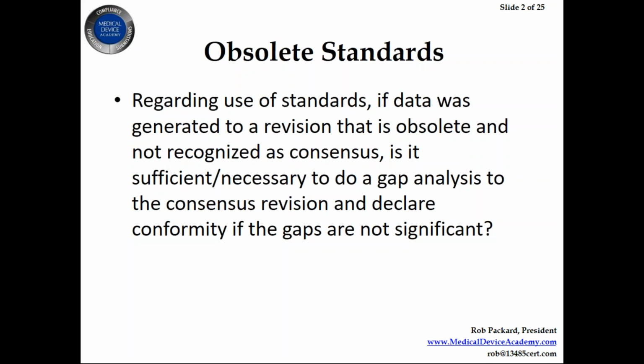So we had to redo all our testing, and it wasn't acceptable to the FDA to submit a gap analysis. We tried that for sterilization because we knew we couldn't complete that in time, and they wouldn't accept it. They said, please provide, after you've completed the testing, resubmit. So we didn't have to pay another fee, but now they're on crunch time trying to finish all the retesting before their 180 days is up, and they may not make it. They may have to pay for the entire submission again and resubmit everything. And if they deliver even 1 day late on the 181st day, your entire submission gets deleted automatically.